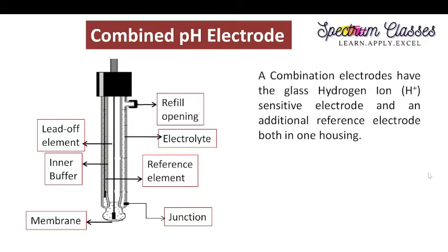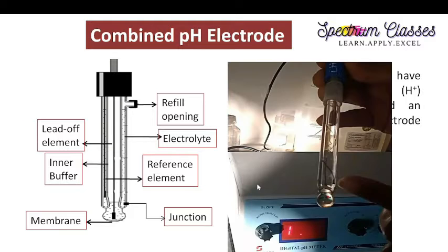Here is the combined pH electrode. A combination electrode has the glass hydrogen ion (H+) sensitive electrode and an additional reference electrode, both in one housing. This is the schematic diagram for the combined pH electrode. Here is the refilling opening, and this is the outer container. Inside the outer container is the filling of electrolyte, which is KCl. Here is the reference electrode which is dipped in this electrolyte, and here is the junction, which serves as the connection between the reference electrode and the working solution. Here is the glass bulb, which has the glass membrane, and here is the lead-off element which is dipped inside the buffer solution.